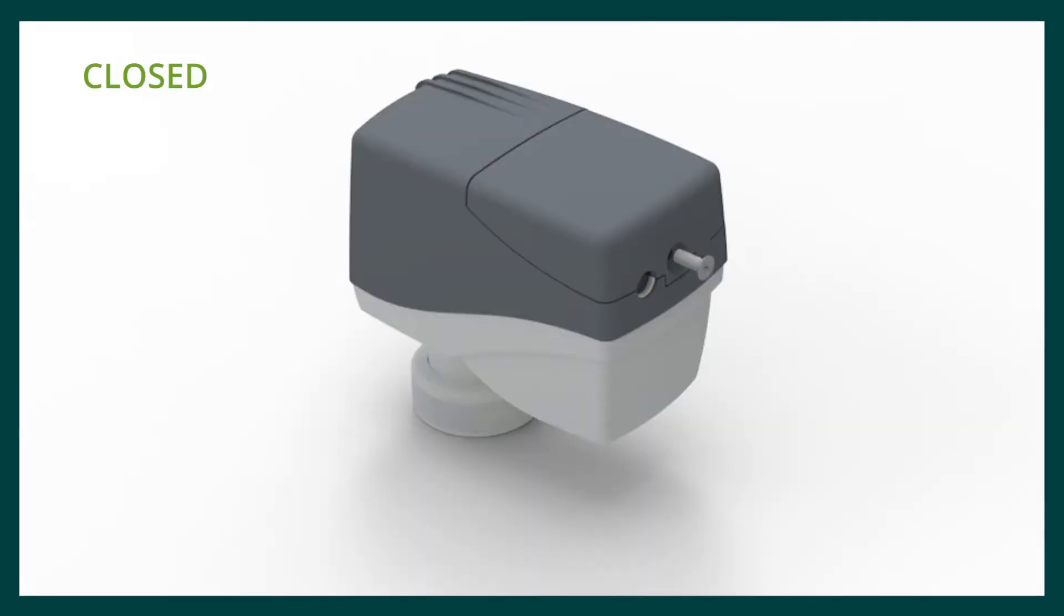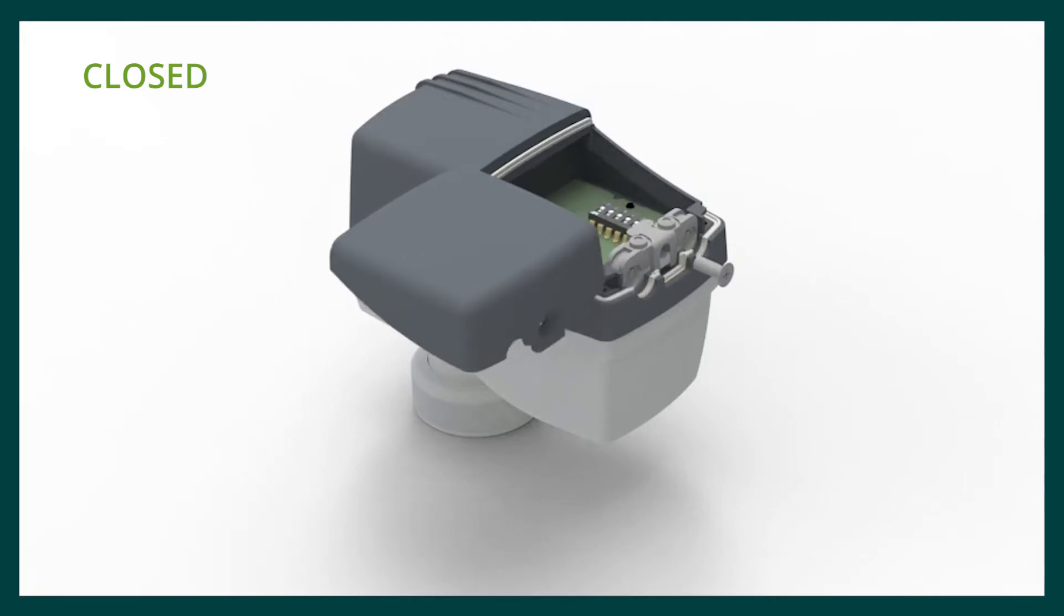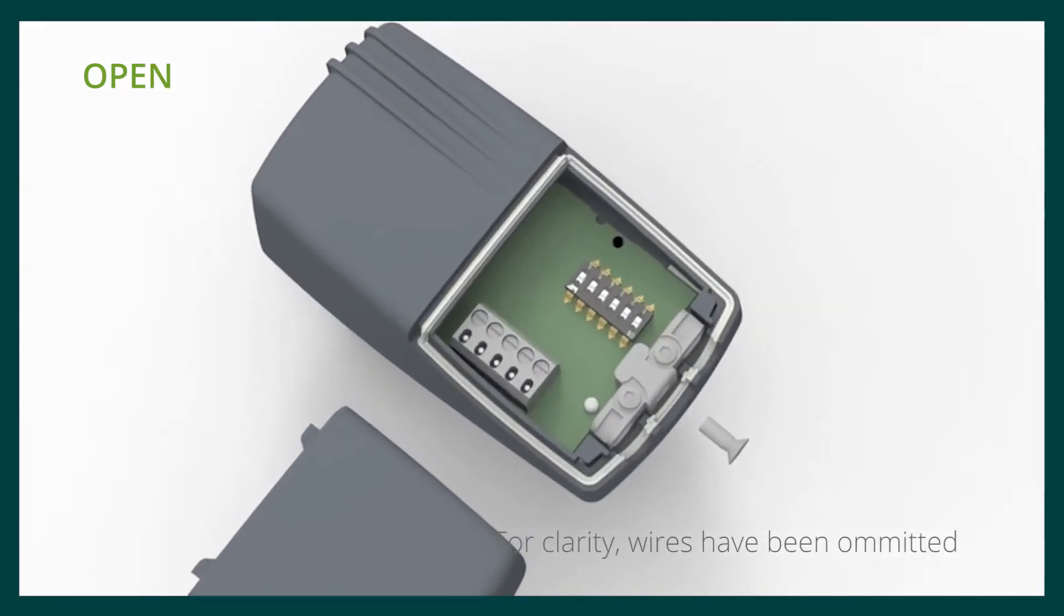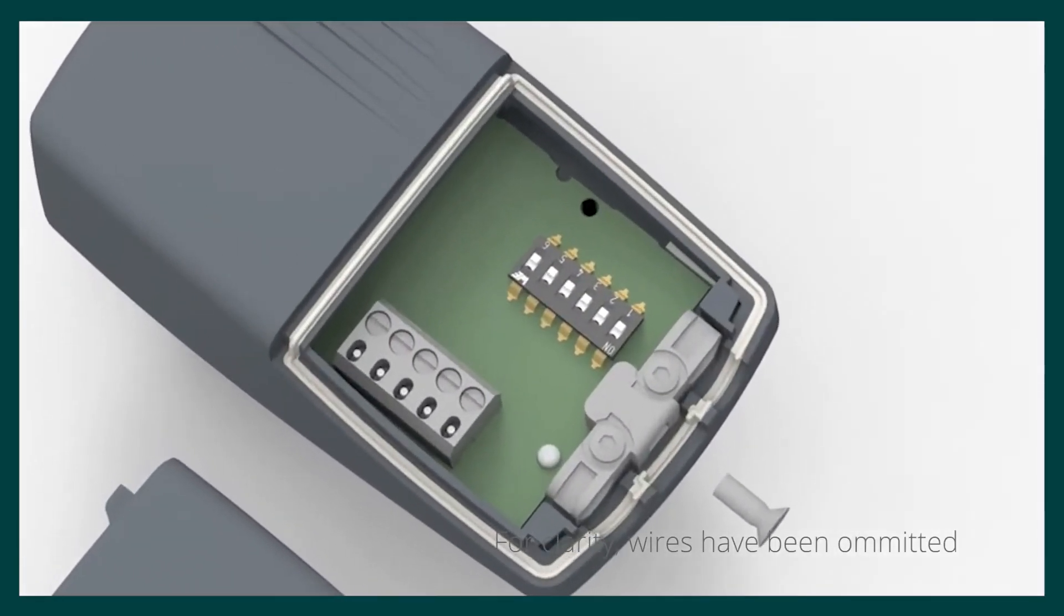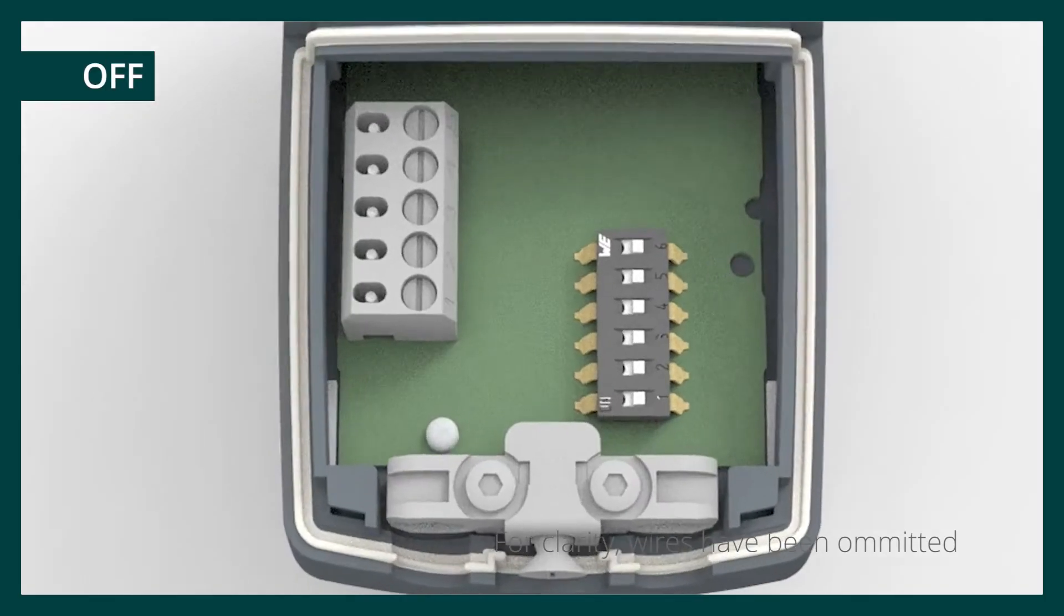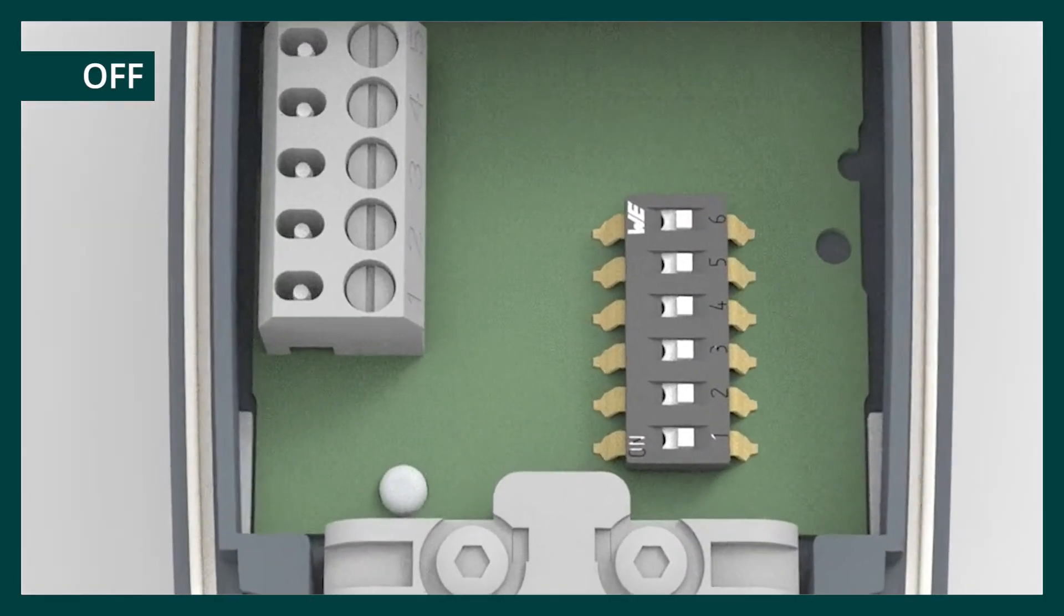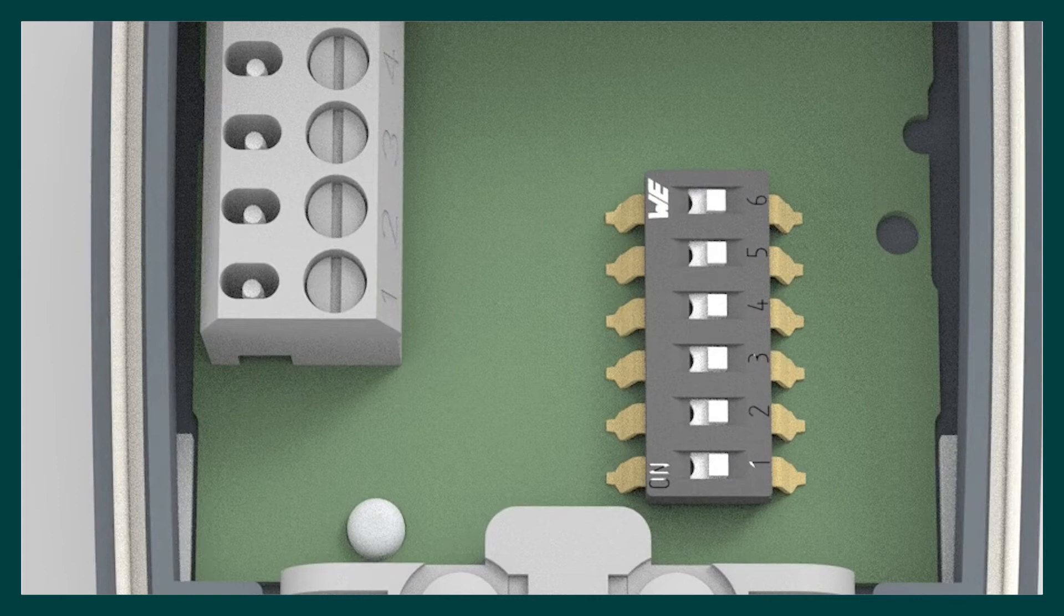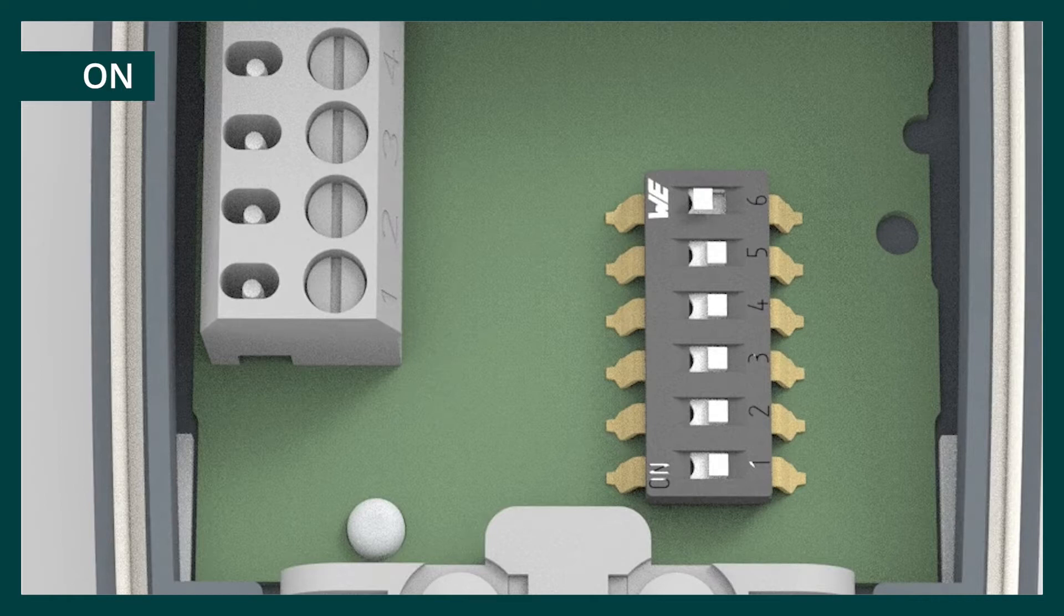To set up the FN02 actuator DIP switches, unscrew the set screw and lift off the cover. The default setting for all the DIP switches is the off position which will satisfy the majority of applications for the green PICV. Switching the DIP switch to the on position changes the function.